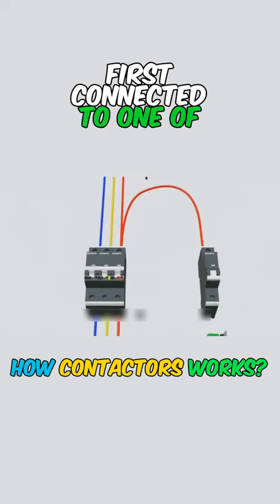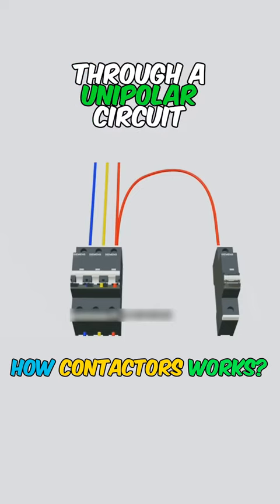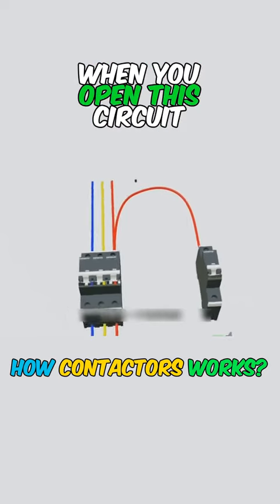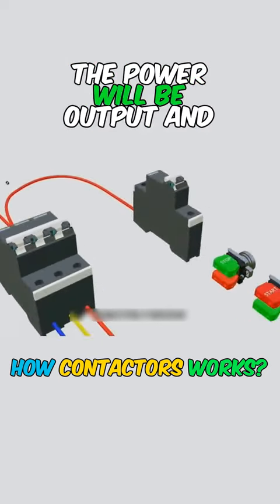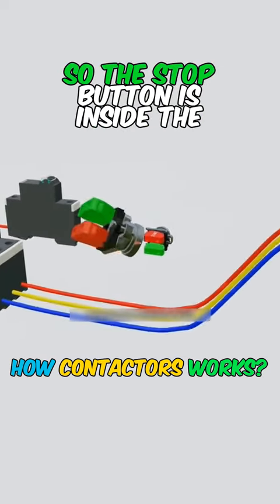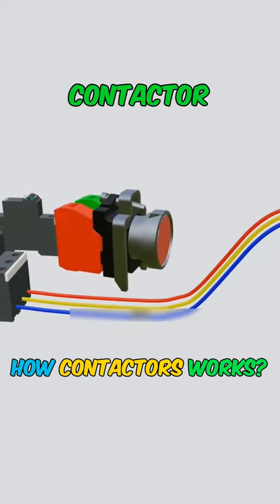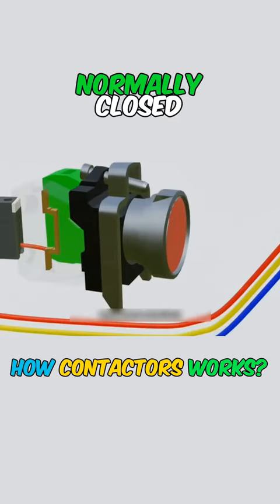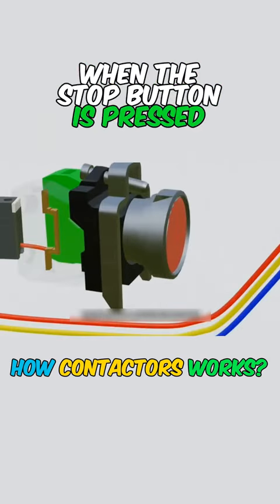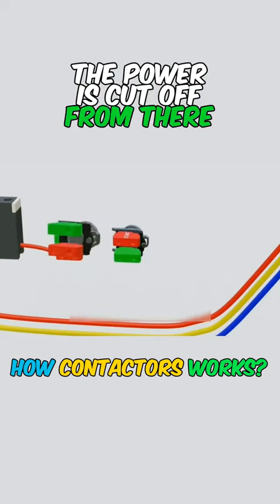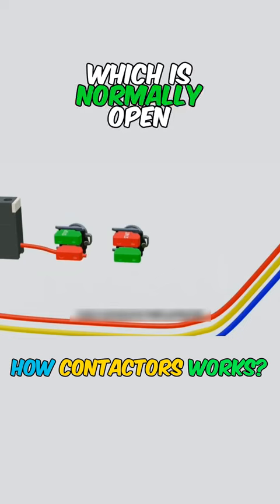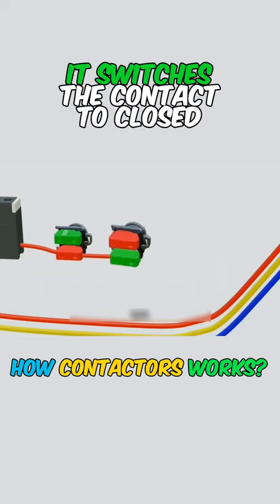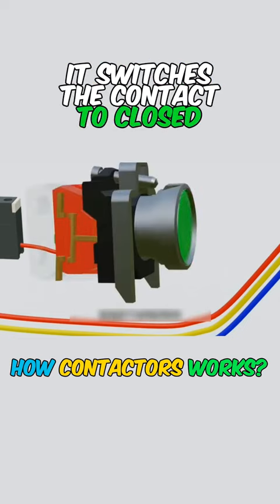First, connect it to one of the phases through a unipolar circuit breaker. When you open this circuit breaker, the power will be output and go through the stop button, so the stop button is inside the contactor. It has a long arm that is normally closed. When the stop button is pressed, the power is cut off from there and goes to the start button, which is normally open.